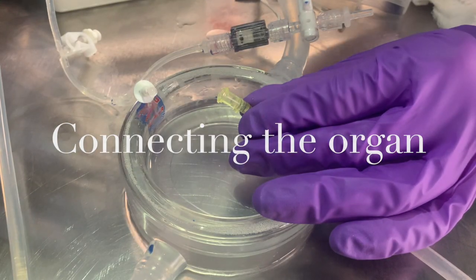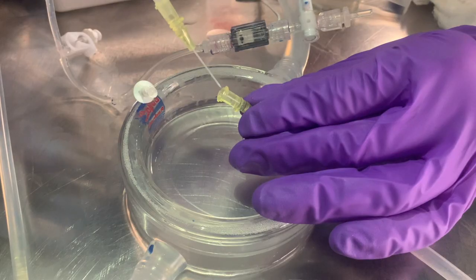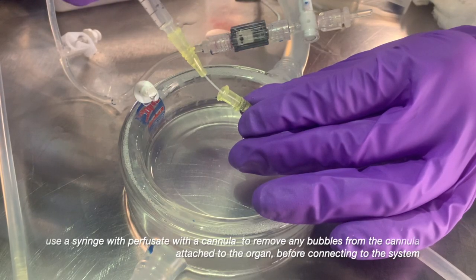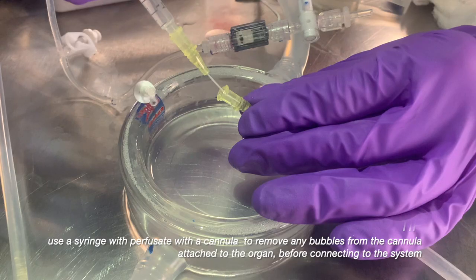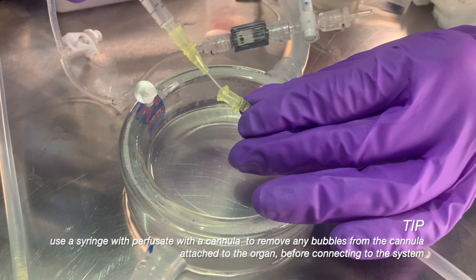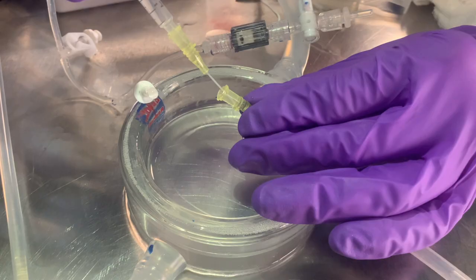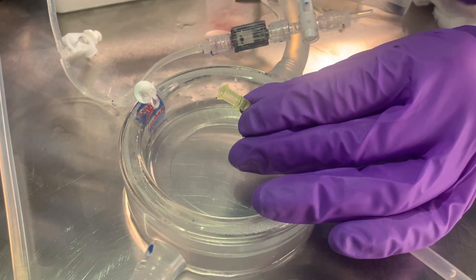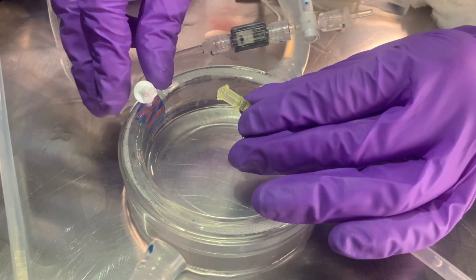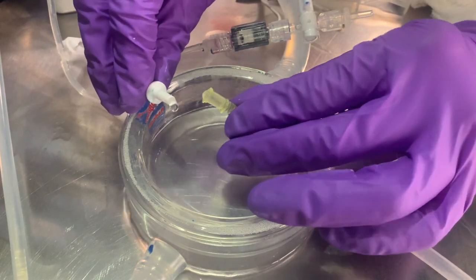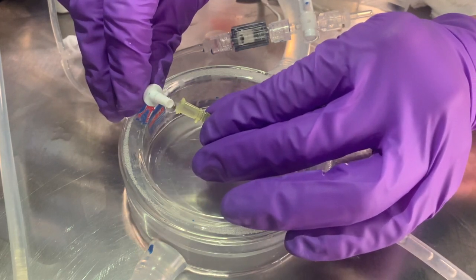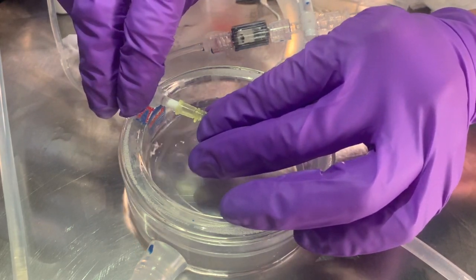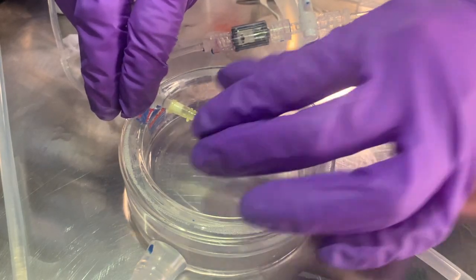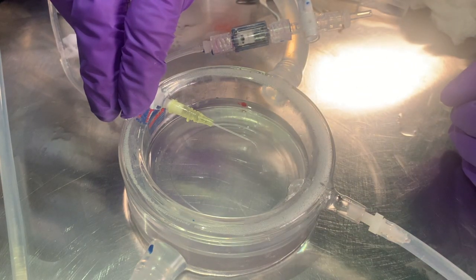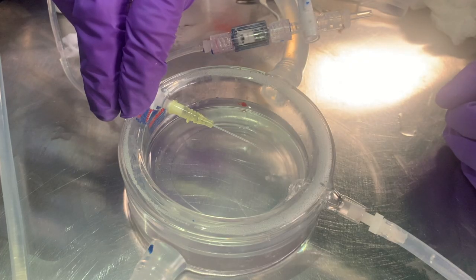When connecting the organ, increase the flow slightly and point both the cannula and the inflow tube in upward directions to avoid air bubbles from entering the system. Make sure that the cannula is filled with liquid, and as liquid slightly overflows from both tubes, carefully slide the cannula onto the inflow tube in one smooth movement. Take care not to manipulate the cannula too much, as this can cause it to dislodge from the organ. Finally, make sure that the cannula is not twisted and uninhibited flow of perfusate is allowed into the organ.